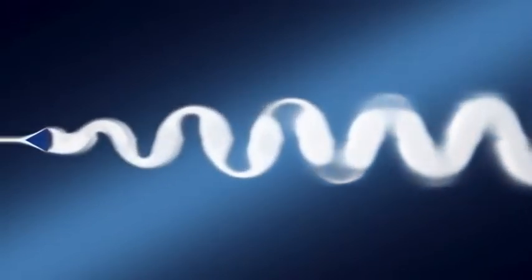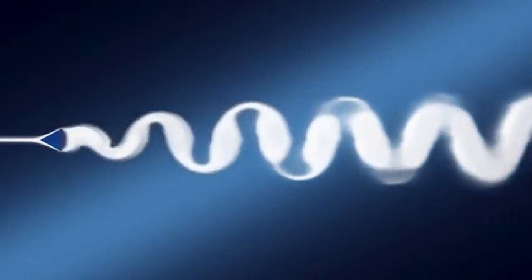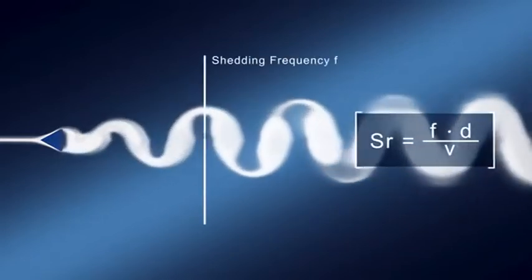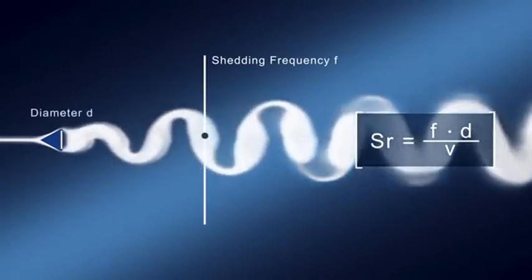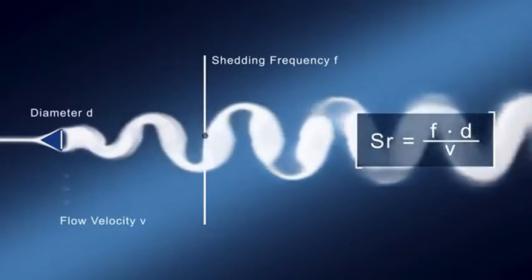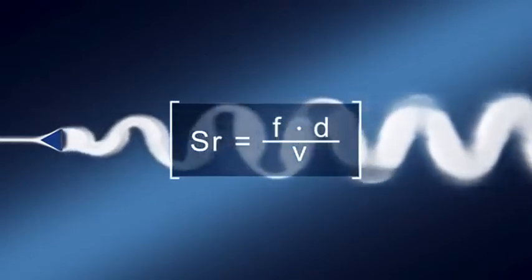Even at low flow velocities a vortex street is formed by oncoming flow of a suitably shaped flow obstruction. Pivotal measuring parameter is the vortex frequency. The Strouhal number is non-dimensional and the result of the shedding frequency multiplied with the bluff body's diameter divided by the flow velocity.